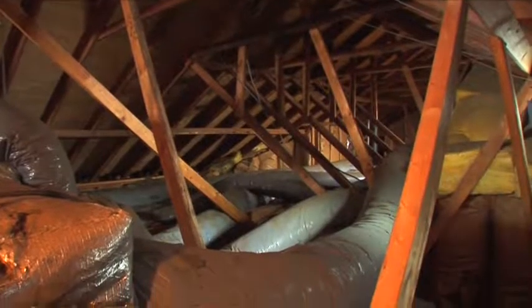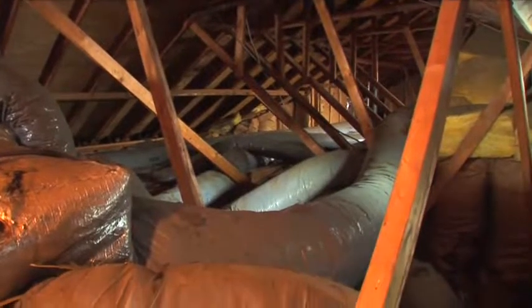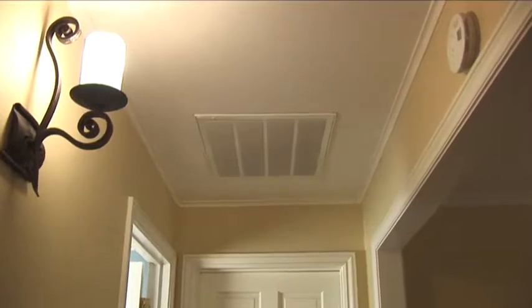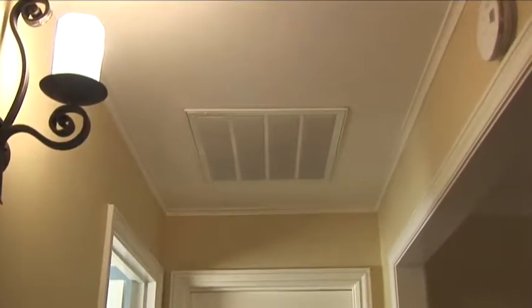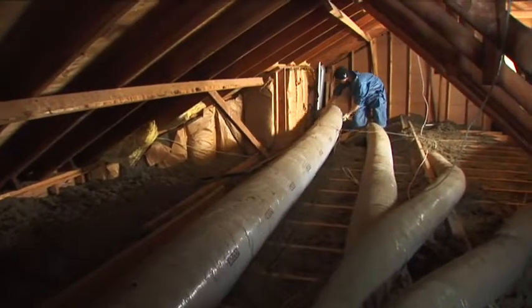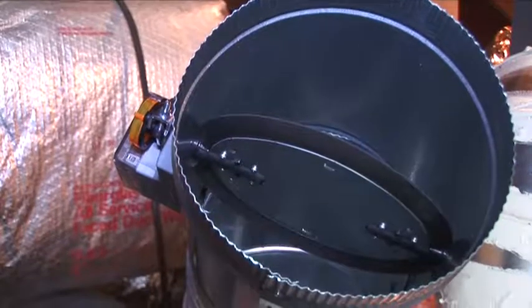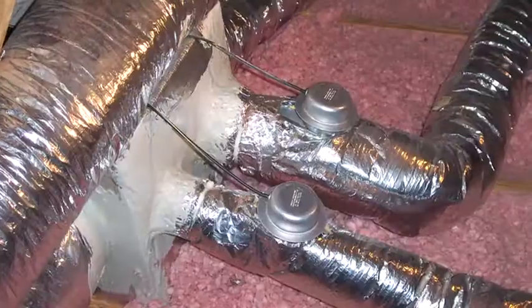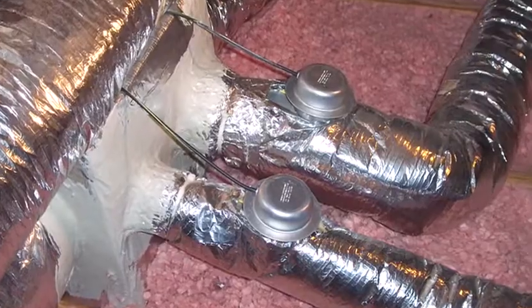Another problem is an overall lack of engineering or design. Many duct systems are undersized for the equipment they're connected to, and the result is a system that's choked and can't move the right amount of air. Some common solutions are adding or enlarging return grills and ducts, and straightening out supply runs. As part of a duct renovation or a new duct system installation, you can install adjustable motor-operated zoning dampers to deliver the right amount of air to each room.